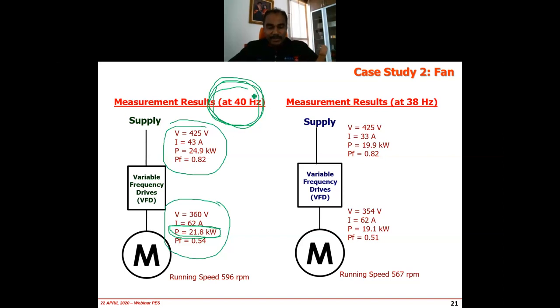Okay? That's number one. The motor is oversized. It's running at a light load. Number two, it is always running at 40 hertz. So what we did was, we said, okay, let's reduce the frequency by 2 hertz. Let's run at 38 hertz. And then we found, wow, look at the reduction of the power. From 24.9, it reduced to 19.9 just by reducing 2 hertz.